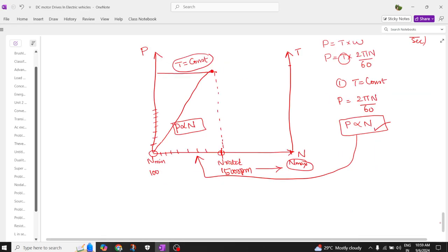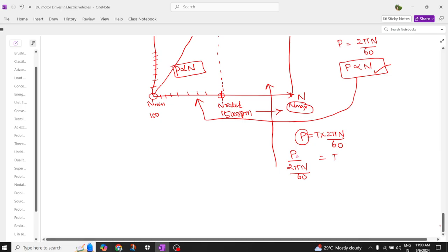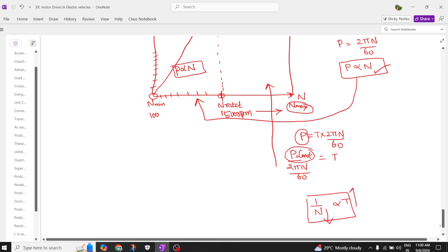In the region beyond rated speed, power equals torque multiplied by 2πn divided by 60. Here we assume power is constant, so torque equals power divided by (2πn/60). Since power is constant, torque is inversely proportional to speed — at low speeds the DC motor offers high torque, and at high speeds the torque is minimum.